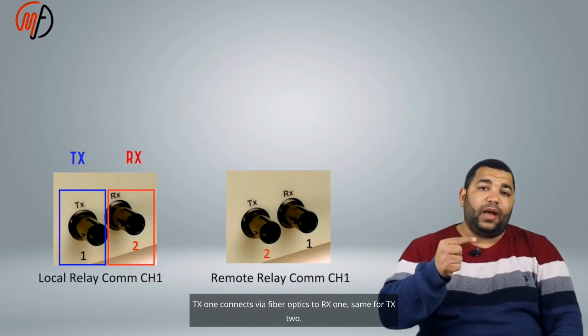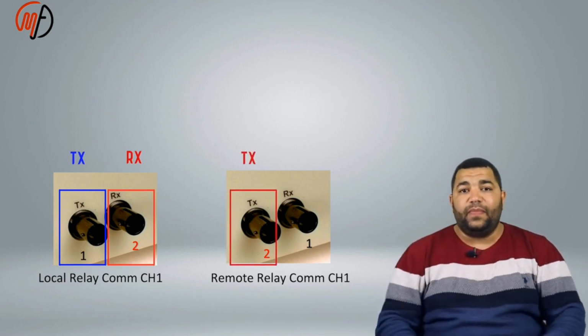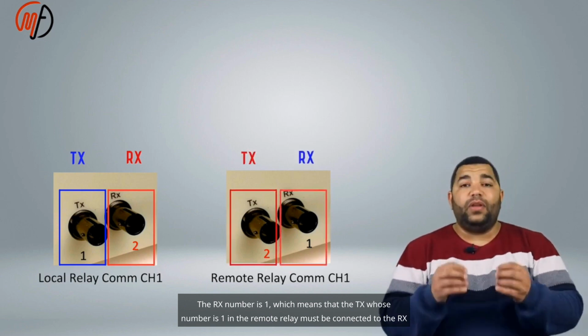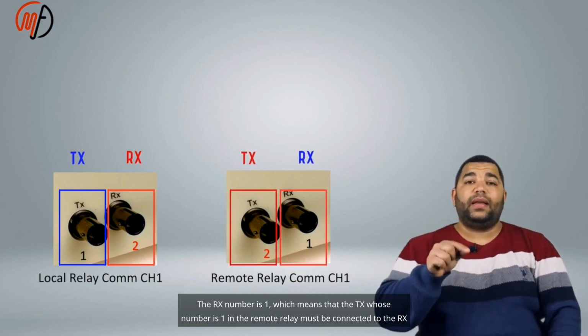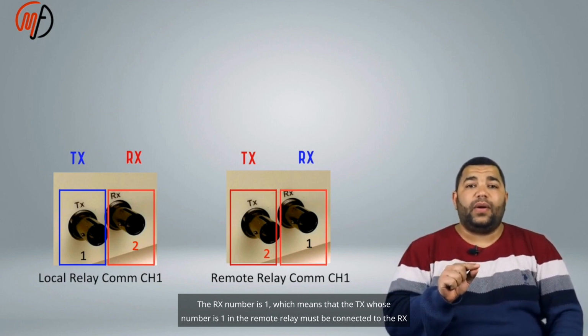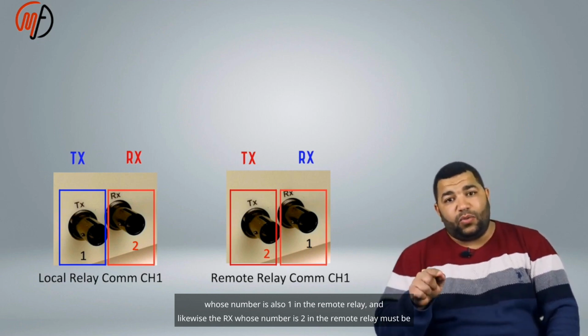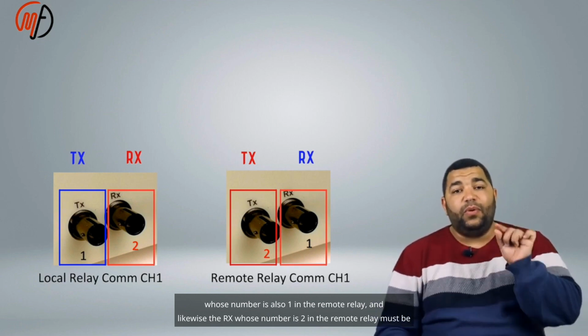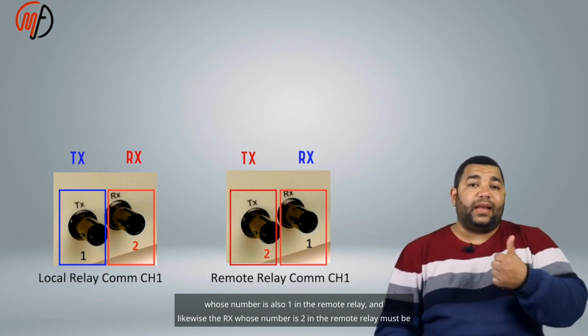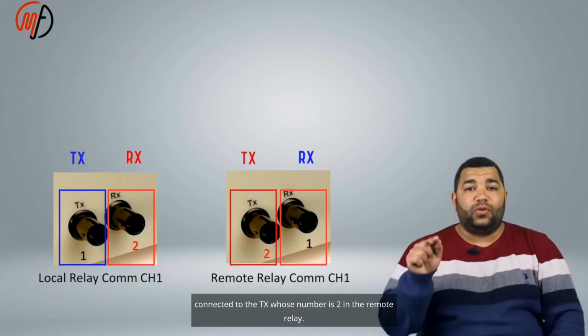TX1 connects via fiber optics to RX1, same for TX2. The RX number is 1, which means that the TX whose number is 1 in the remote relay must be connected to the RX whose number is also 1 in the remote relay, and likewise the RX whose number is 2 in the remote relay must be connected to the TX whose number is 2 in the remote relay.